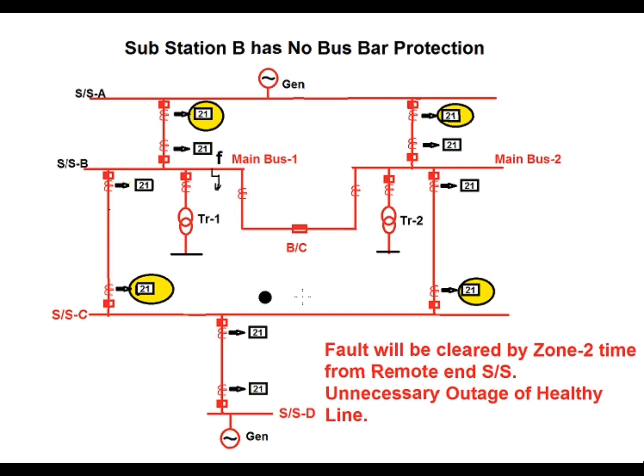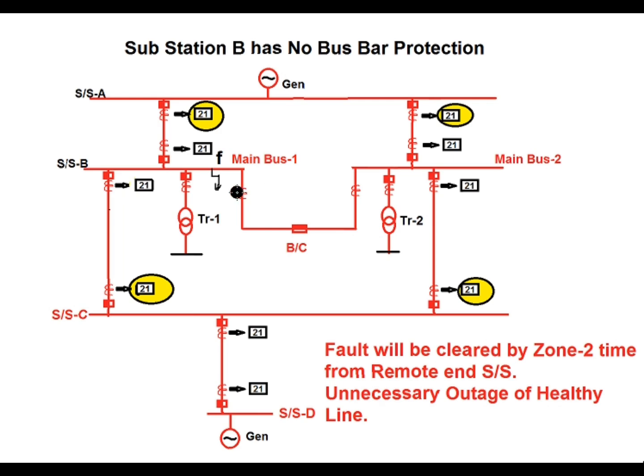The remote end feeder will sense this fault at zone 2 location. Zone 2 is normally given a time delay of 350 to 500 milliseconds, so this fault will be cleared from the remote end feeder at zone 2 time. All feeders connected to the substation will trip from the remote end substation under zone 2 time. Due to absence of bus bar protection, all feeders connected to main bus 1 and main bus 2 will be tripped from zone 2, causing unnecessary outage of healthy feeders and outage of transformer 2.